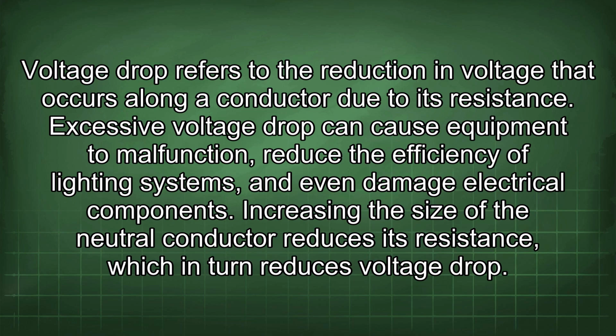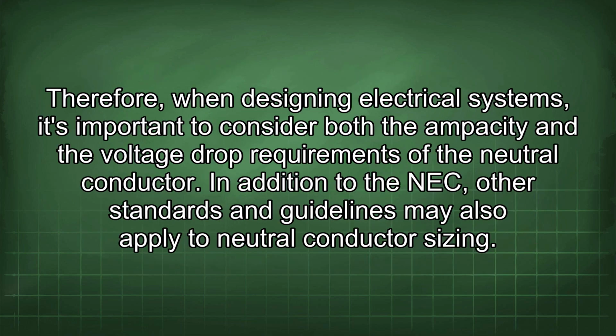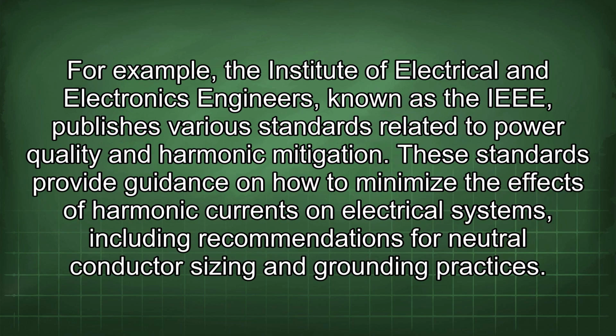Increasing the size of the neutral conductor reduces its resistance, which in turn reduces voltage drop. Therefore, when designing electrical systems, it's important to consider both the ampacity and the voltage drop requirements of the neutral conductor. In addition to the NEC, other standards and guidelines may also apply to neutral conductor sizing. For example, the Institute of Electrical and Electronics Engineers, known as the IEEE, publishes various standards related to power quality and harmonic mitigation. These standards provide guidance on how to minimize the effects of harmonic currents on electrical systems, including recommendations for neutral conductor sizing and grounding practices.